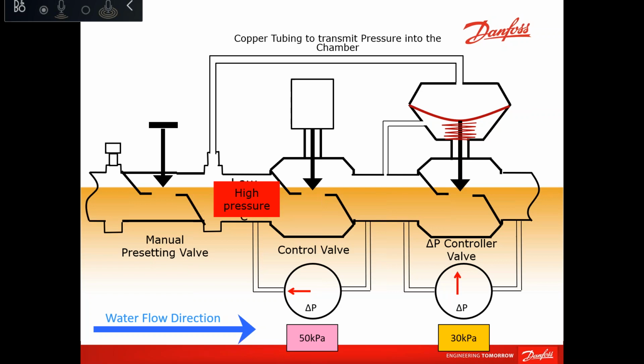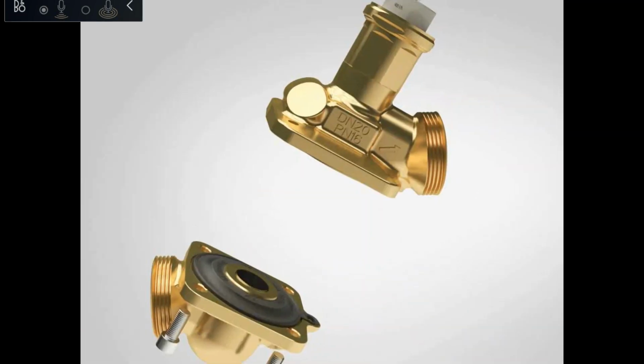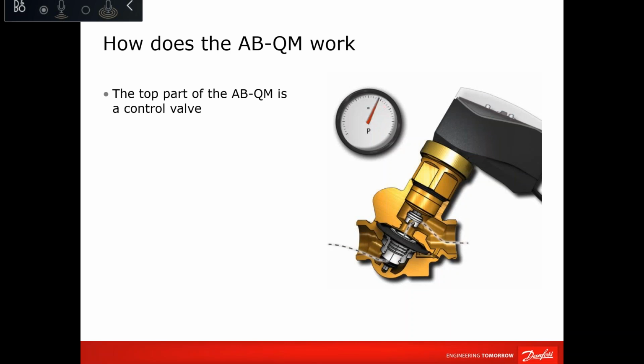What is the cone material? The cone material. Yeah, we have brass for the small sizes in the control part, and the seat is dezincification-resistant brass as well. In the DPCV part, because the valve is a combination, which I will show here, this one is brass, and the seat is dezincification-resistant brass. The disc and the cone of the pressure controller are stainless steel. The spring is stainless steel, and the membrane is vulcanized EPDM. So this is for sizes up to DN32.